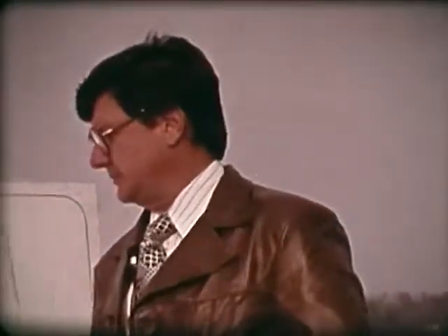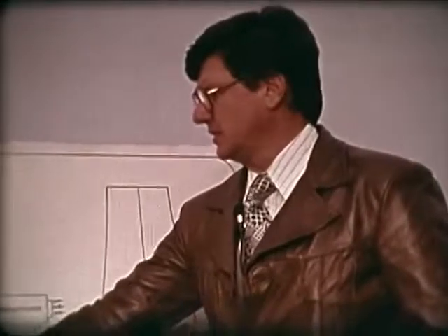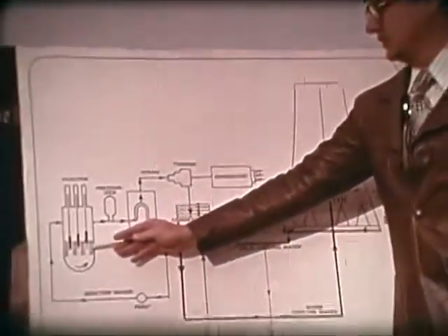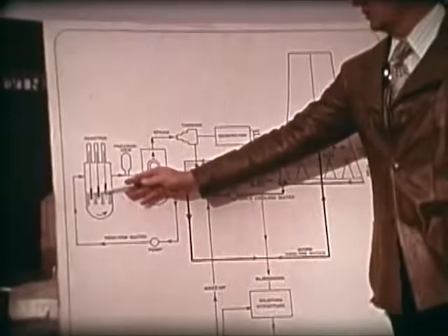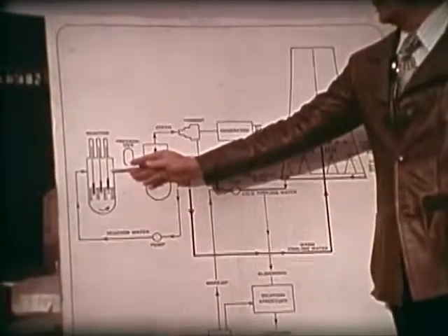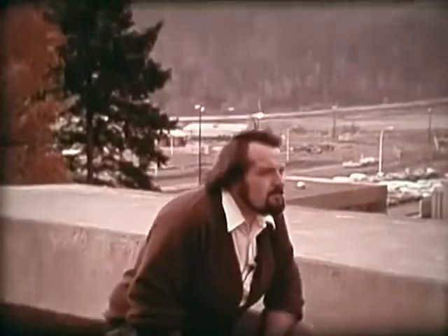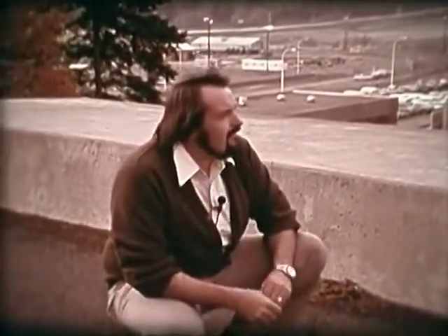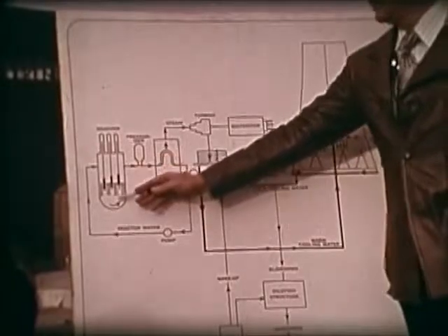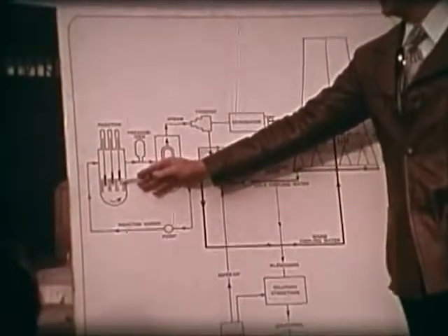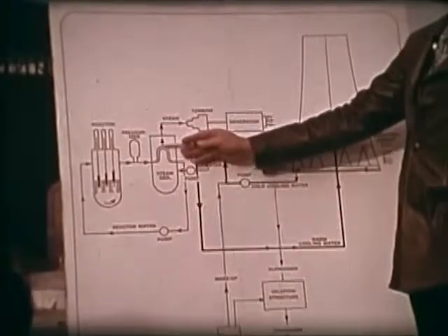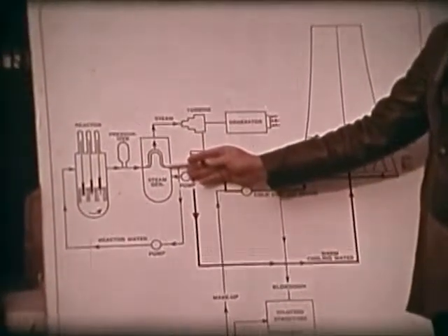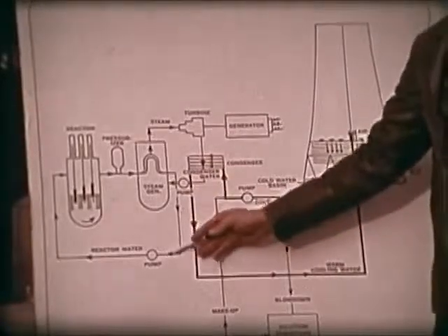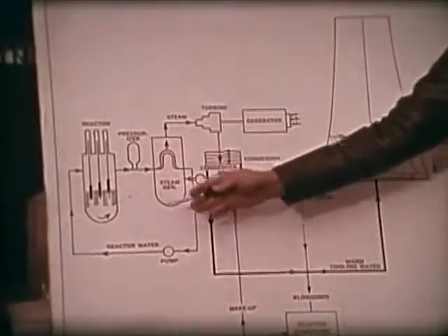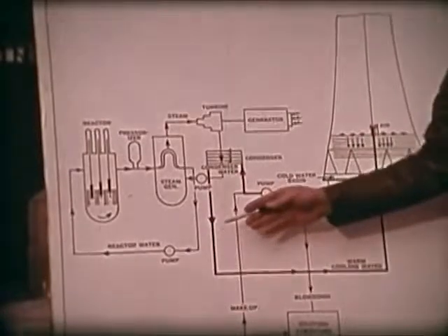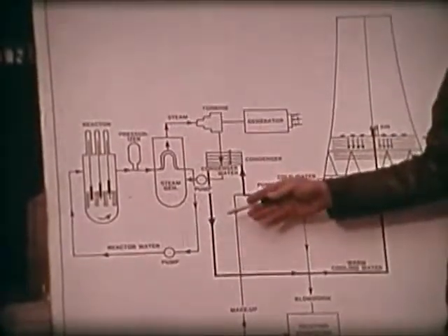The reactor itself includes the reactor vessel containing the reactor core, the fuel, and the control rods for control of the reactor. This is all filled with water, which is under pressure so it remains liquid during operation of the plant. This water circulates through the reactor core where heat is picked up, through a steam generator where it gives up heat to the secondary system, then back through a reactor coolant pump where it's pumped back through the reactor core again. This is one system, which we call the primary system, or the reactor coolant system.